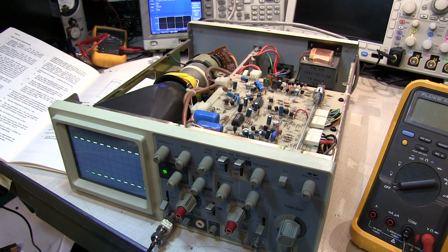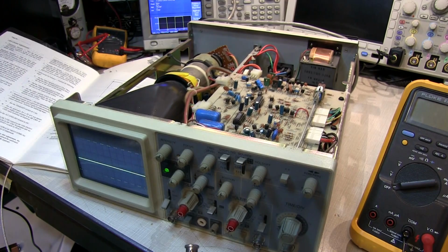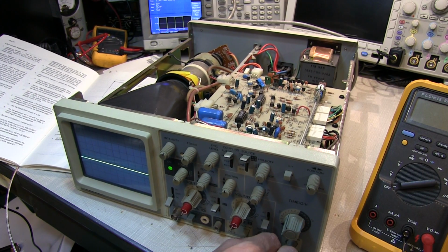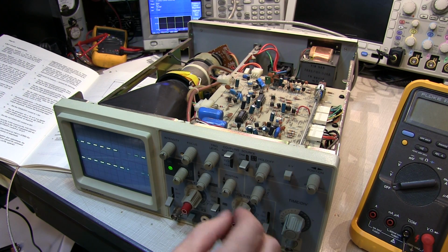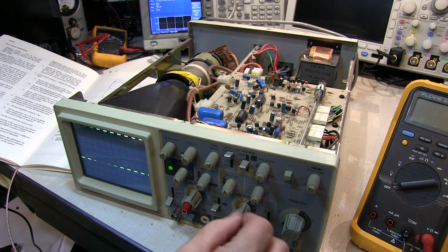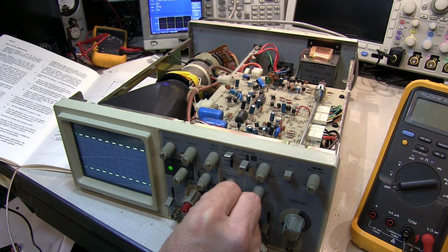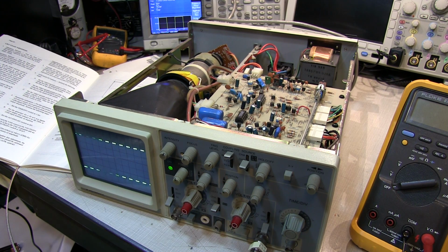And we need to repeat that for channel B. Okay, moving that signal over to channel B. So the vertical mode to channel B, DC couple it, trigger on channel B, and let's set that to 10 millivolts a division, and let's see where we are. It looks like this channel is very good. I've got precisely 5 divisions vertical deflection, so there's no adjustment needed on channel B.